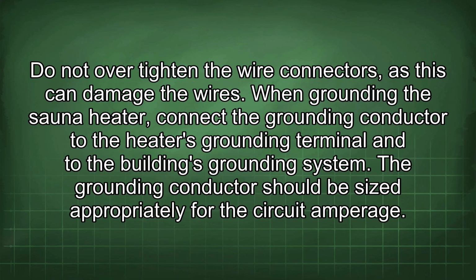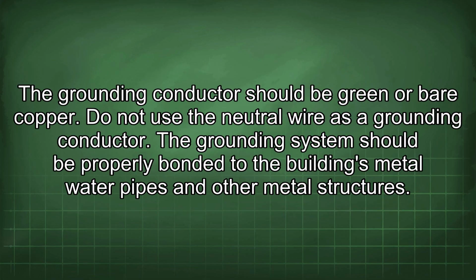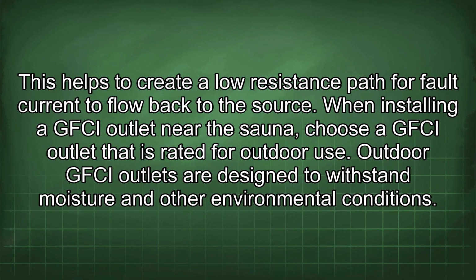When grounding the sauna heater, connect the grounding conductor to the heater's grounding terminal and to the building's grounding system. The grounding conductor should be sized appropriately for the circuit amperage. The grounding conductor should be green or bare copper. Do not use the neutral wire as a grounding conductor. The grounding system should be properly bonded to the building's metal water pipes and other metal structures. This helps to create a low resistance path for fault current to flow back to the source.